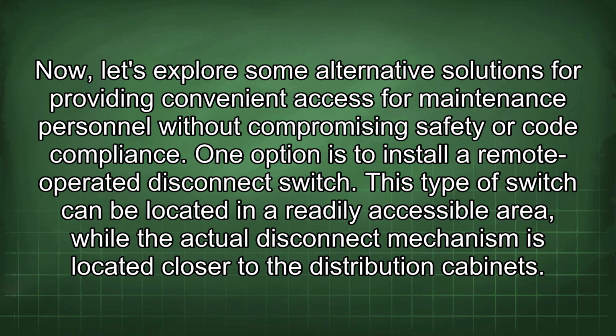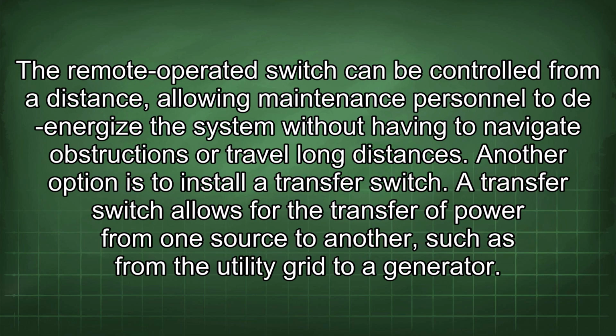One option is to install a remote-operated disconnect switch. This type of switch can be located in a readily accessible area, while the actual disconnect mechanism is located closer to the distribution cabinets. The remote-operated switch can be controlled from a distance, allowing maintenance personnel to de-energize the system without having to navigate obstructions or travel long distances.